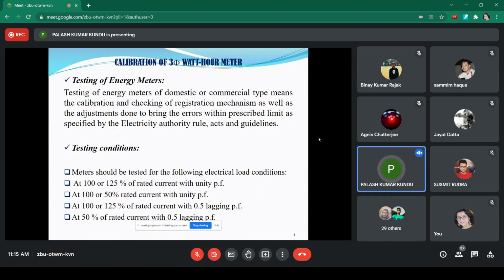Again, the power factor should be varied, with a 0.5 lagging power factor condition at the same loading conditions, that is 100% or 125% of the rated load current, as well as 50% of the rated load current, with 0.5 lagging power factor. So these are the testing conditions according to the IEC rule.